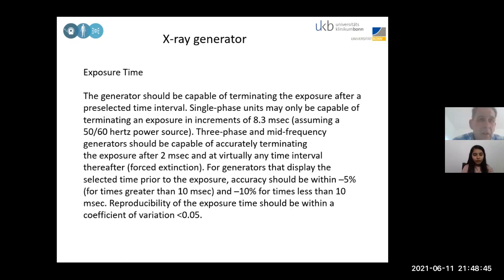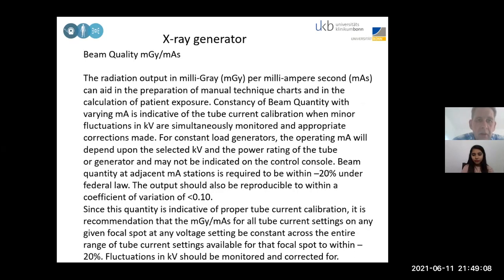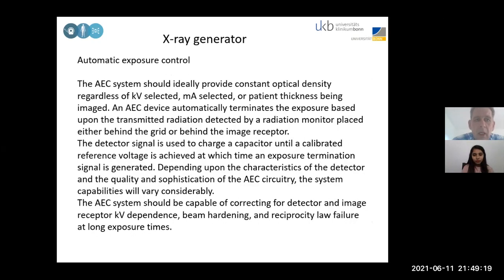So let me say 120 kV image, and your auto exposure control says 8.3 milliseconds. Then you have to be sure that it is also 8.3 milliseconds and not 10. So that is something you should also check. Then there is something called the milligray versus mAs. This is more or less the output measured with an ionization chamber. And the automatic exposure control, I already noticed, is something you really have to check, whether the automatic control is working properly.